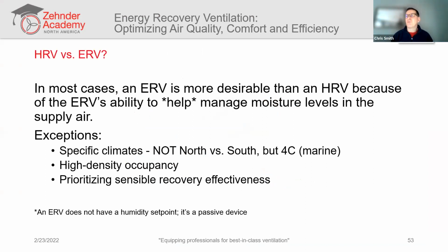So which should we look for in our designs? Should we look for an HRV or an ERV? Well, in most cases, an ERV is more desirable than an HRV because of the ERV's ability to help manage moisture levels in the supply air. I say help because we need to remember that an ERV doesn't have a humidity set point. It's not a humidifier or a dehumidifier, but it's a passive device that can very effectively help mitigate the need to run other equipment as much to control the humidity levels. So an ERV is usually the most desirable choice.